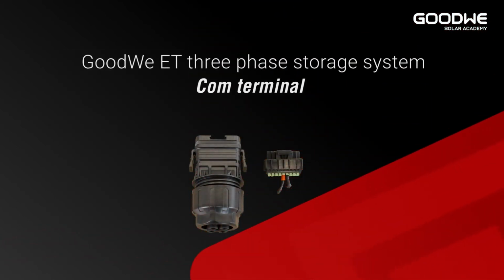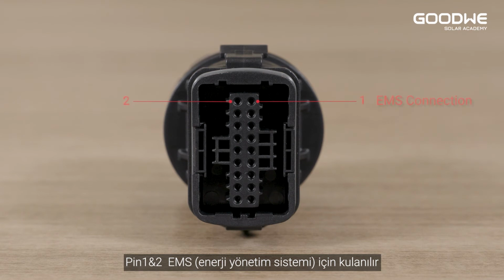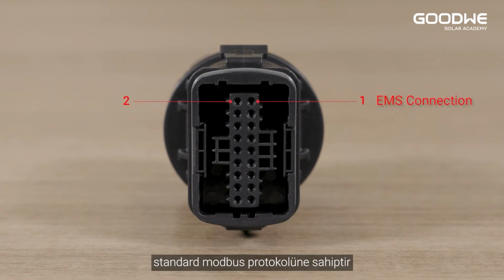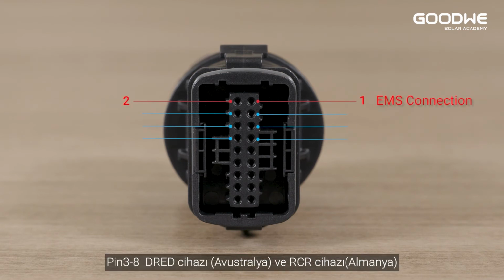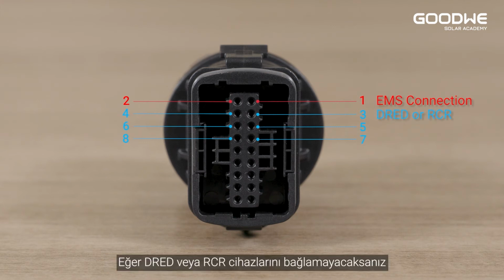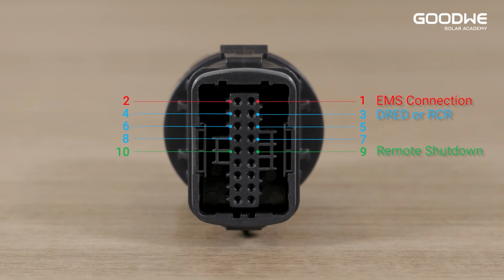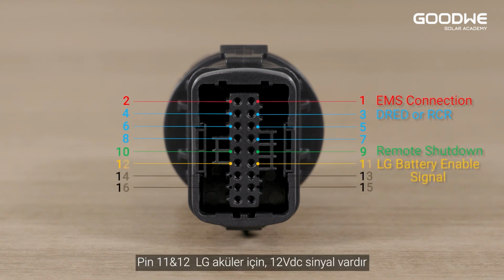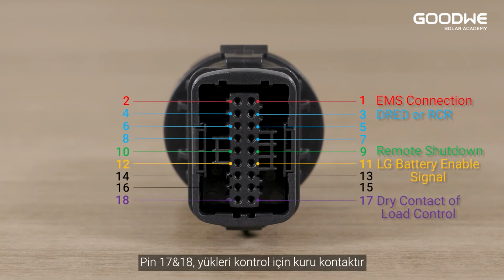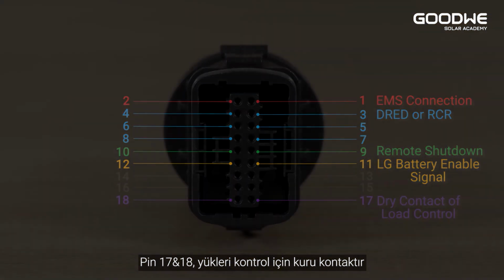COM terminal. Pin 1 and 2 for EMS connection, using standard Modbus protocol. Pin 3 to 8 for DRED device and RCR device. If you do not connect a DRED or RCR device, do not remove the resistor between pin 7 and 8. Pin 9 and 10 for remote shutdown device. Pin 11 and 12 for LG battery, it is a 12V DC enable signal. Pin 17 and 18, it is a dry contact of load control function.